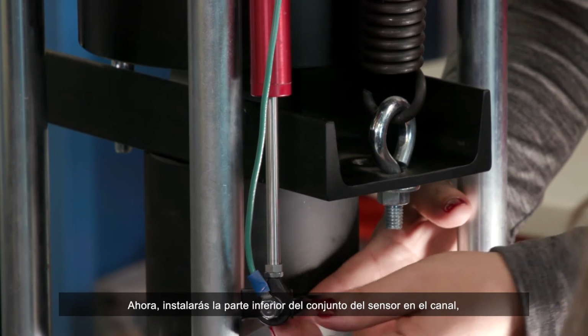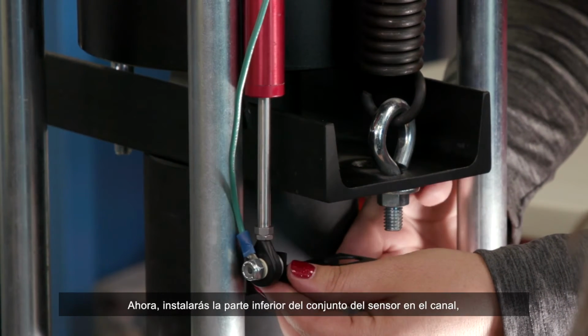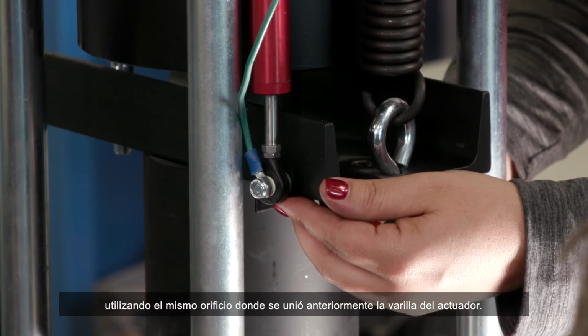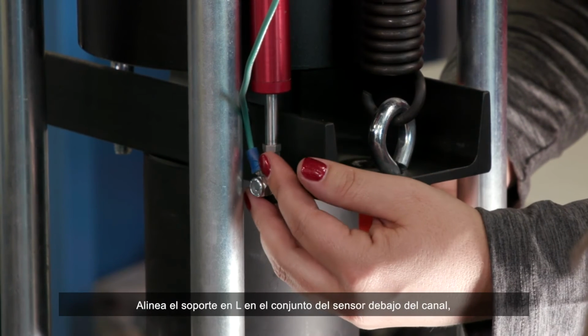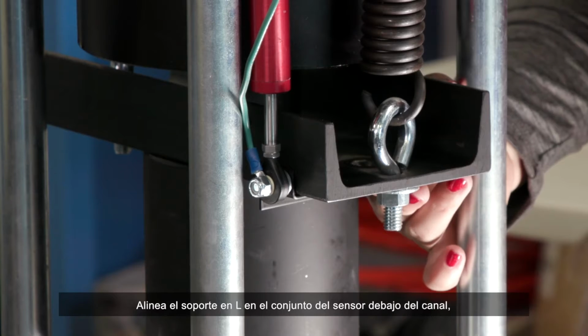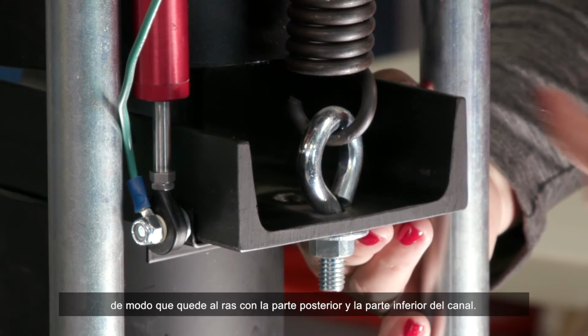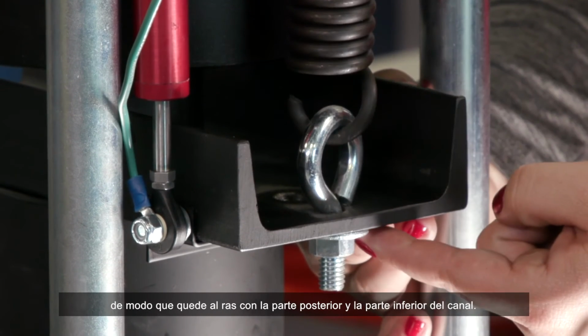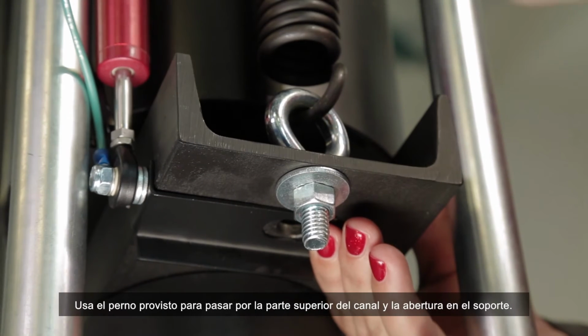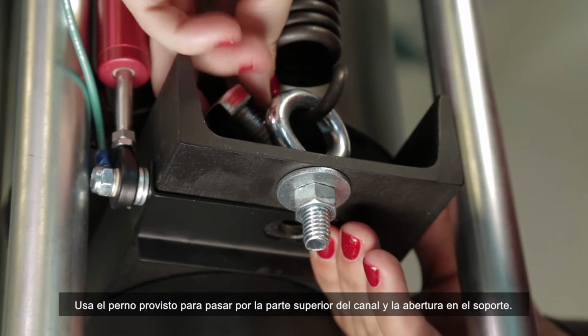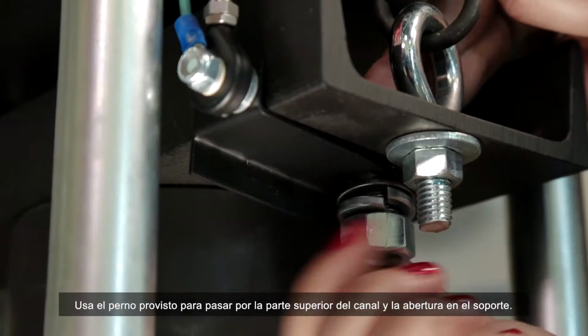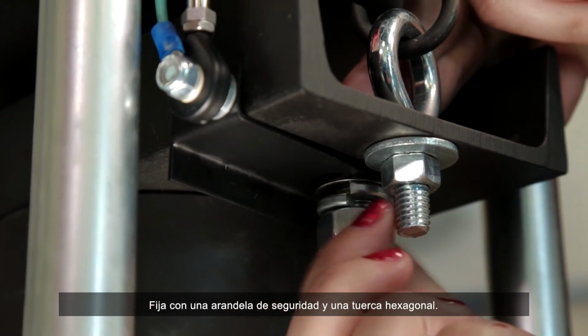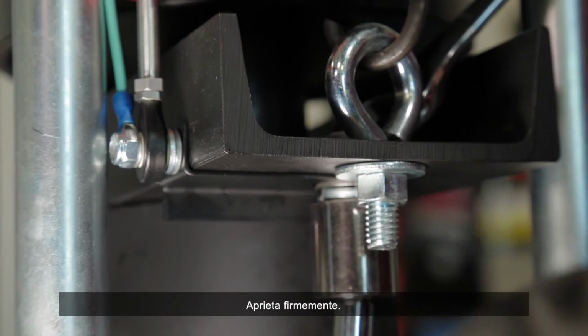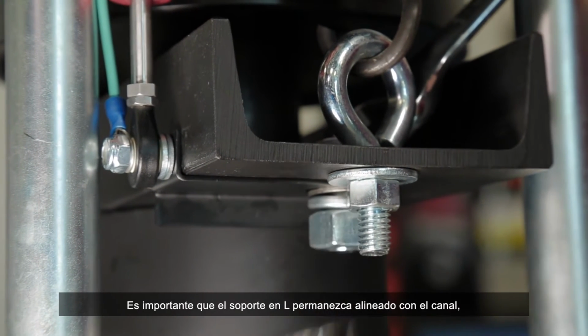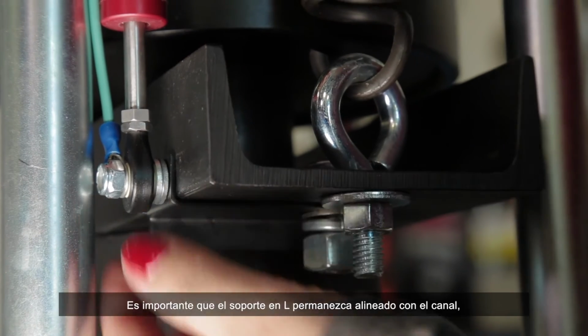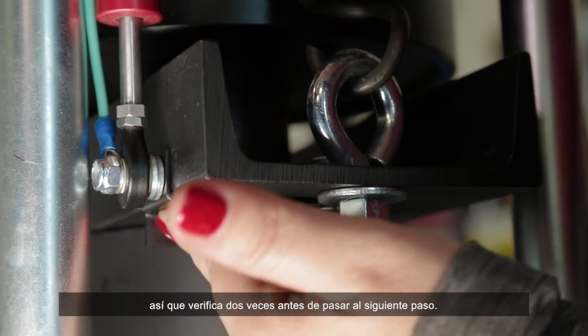Now you'll install the bottom of the sensor assembly to the channel using the same hole that previously attached the actuator rod. Line up the L bracket on the sensor assembly under the channel so that it sits flush against both the back and bottom of the channel. Use the bolt provided to go through the top of the channel and the opening in the bracket. Attach with the washer, lock washer, and hex nut. Tighten firmly. It's important that the L bracket remain flush with the channel, so double check before moving on to the next step.